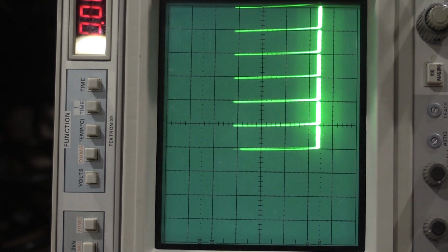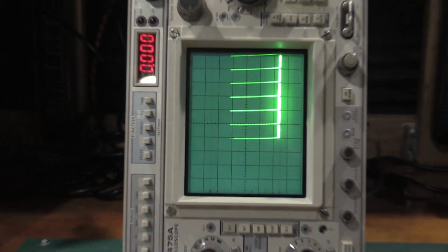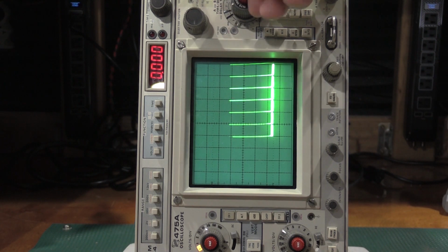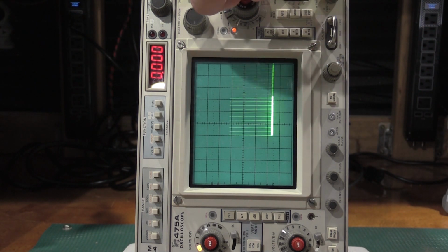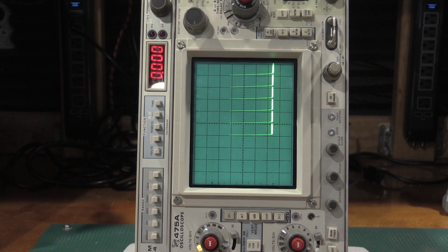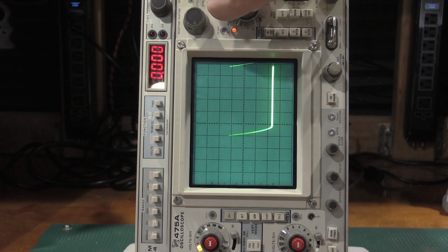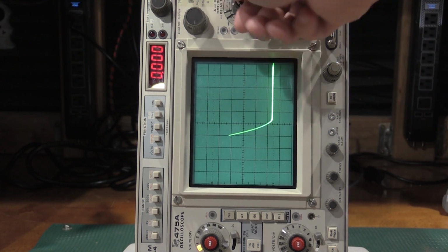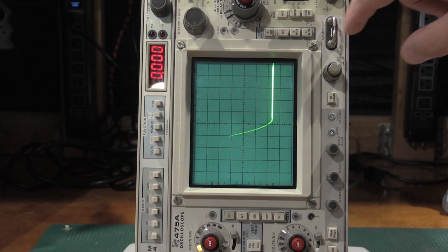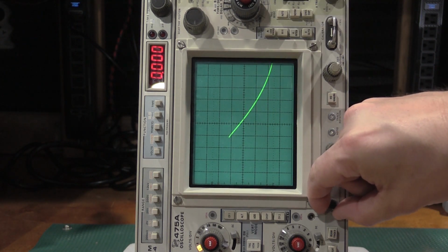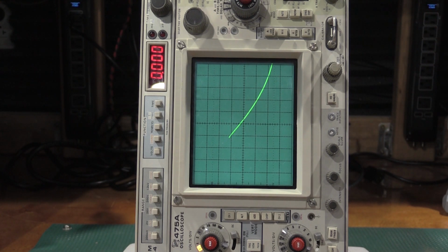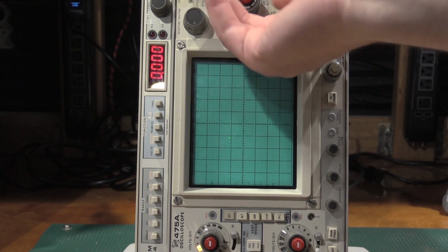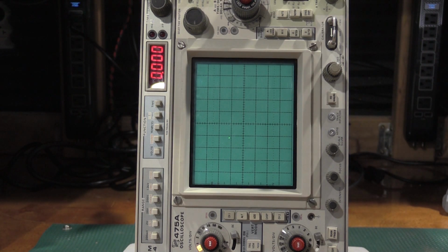Okay, there we go. All right, so we check the variable. Zoom out for this. Check variable. And 10 millisecond time marks. Bounce this up to 10. Pull this back. Less than 4 divisions. That passes. A intensified 0.2. B time, 1 mic. B trigger source starts after delay. Yes. And it wants 0.1.